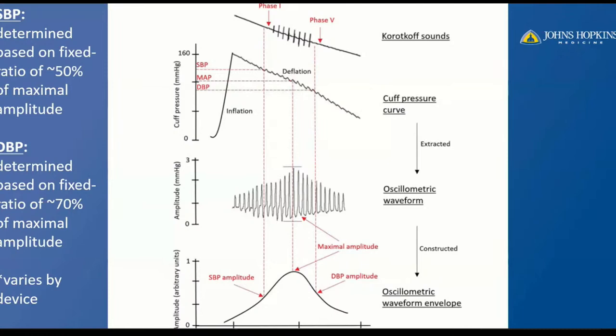These fixed ratio coefficients vary from device to device, but typically systolic blood pressure is determined based on a fixed ratio coefficient of about 50% of the maximal amplitude, while diastolic blood pressure is at about 70% of the maximal amplitude.